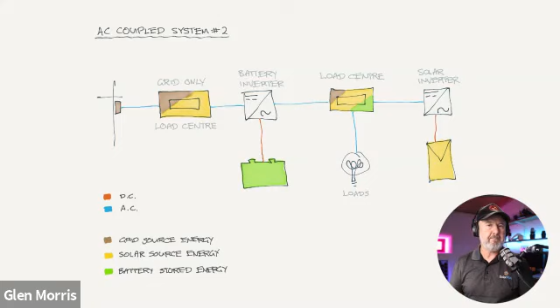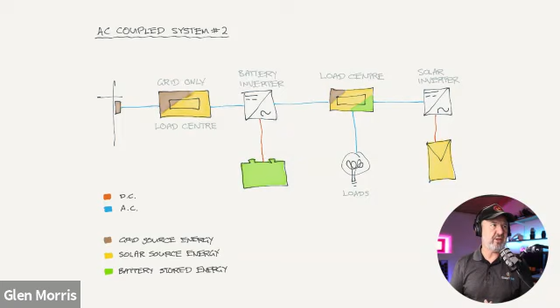Basically there's no separation in certification whether you're using a solar inverter or a battery inverter, simply that if you have something connected in parallel to the grid, it needs to comply with these technical certifications. I should add that you can't assume all battery inverters can do this. It's a special requirement, and they do have to get certified, the same as solar inverters.